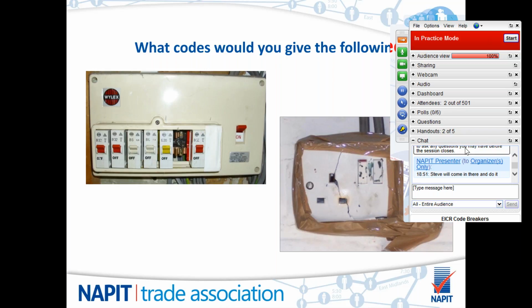What we've got, surrounding the obvious distress to the socket, is packing tape. Packing tape's nowhere near PVC tape, and PVC tape wouldn't be thick enough on one coating to provide protection against electric shock, against somebody pushing against the contacts within there. That would definitely be C1. It is a danger to life, and therefore should be coded as such.